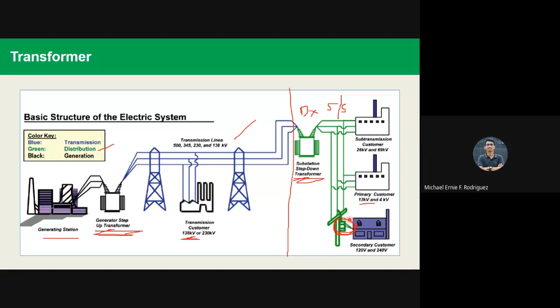A second transformation takes place at the distribution transformers, which are connected to the primary feeders. This transformer steps down the voltage to a value suitable for utilization at the consumer's premises. So the voltage is stepped down from 13.2 kilovolts to 240 volts, which we can then use at home. So there's a step-up for the transmission line, then a step-down for distribution, and another step-down for use in our homes.